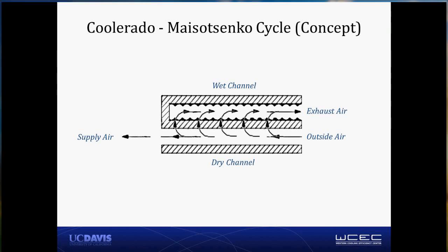They bring in outside air through that primary channel, and instead of allowing all of it to pass through to the product side or the supply air side of the system, some of that air, as it cools down, is scavenged and carried over to the secondary channels. It comes in at a wet bulb temperature that's lower than the outside air condition, and then passes through the secondary channel in contact with water, allows evaporation, and doing the process in this way allows you to drive to a significantly lower temperature for the outlet, the product, or the supply air on the primary side of that system. Under certain scenarios, they can definitely reach below the wet bulb temperature for that product air.